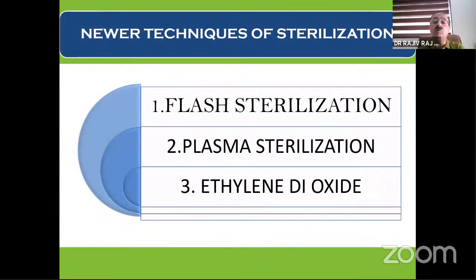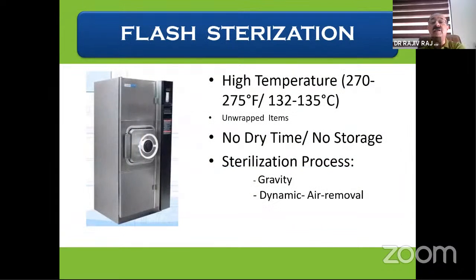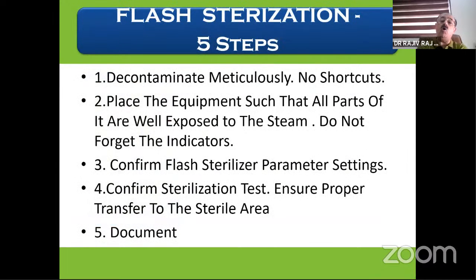The newer techniques include flash sterilization, plasma sterilization, and ethylene dioxide. Now, flash sterilization is again a steam sterilization. There is no drying time, there is no storage time, and the process is either gravity or dynamic removal of the air. Now, there are 5 steps that everyone must remember and make sure it's enforced in your theaters, so that if you are doing flash for any reason, then you are not missing the mark of sterilization.